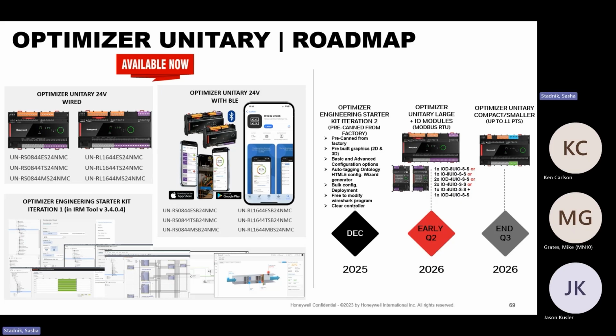And between this controller and this controller, there's a lot of sizing points in it. How many points of control does this thing have? 24 max for the moment. What happens if you need more? For the moment, you need this one with IOs. So there's a gap. To ease that gap, and because what are the needs of more than 24 points of control in HVAC industry? Well, larger air handling units, right?